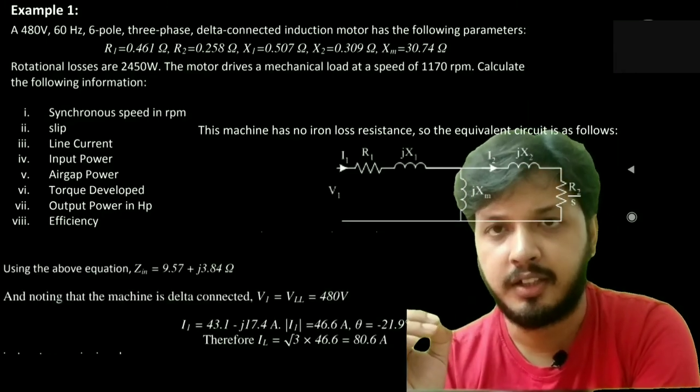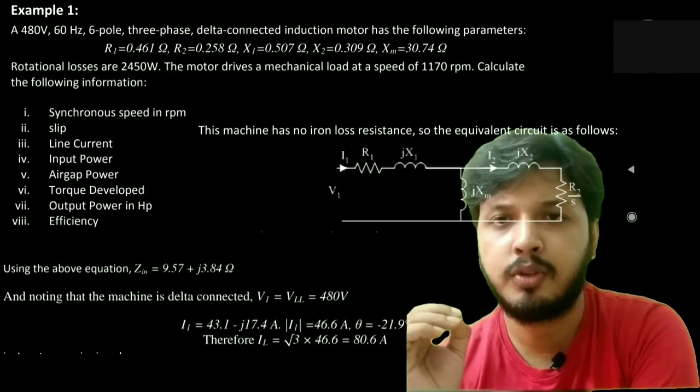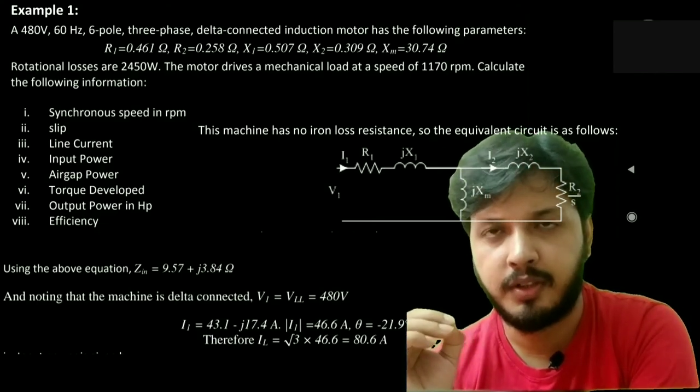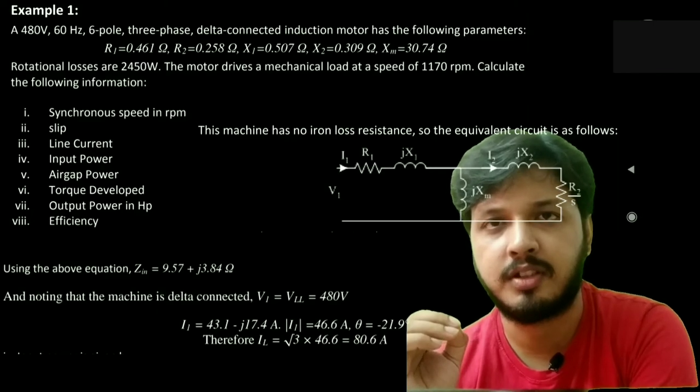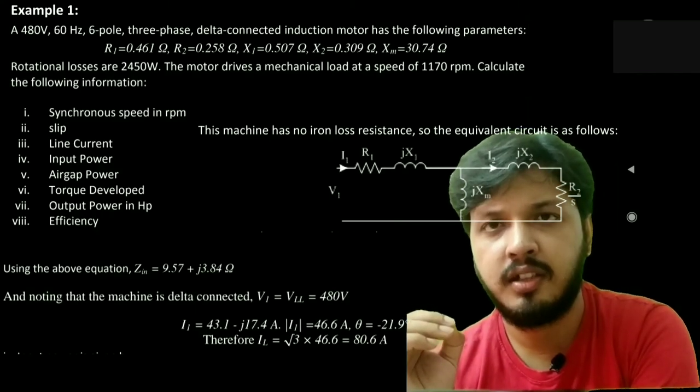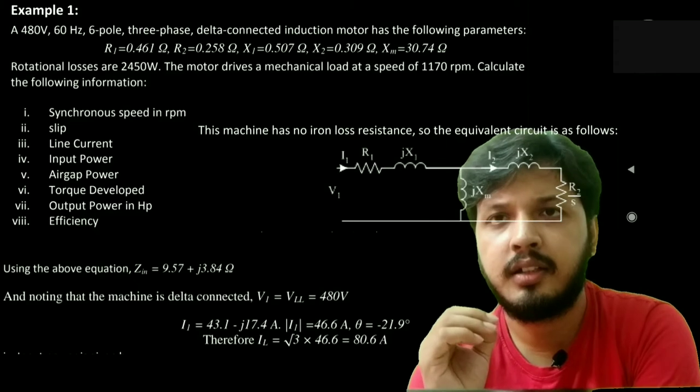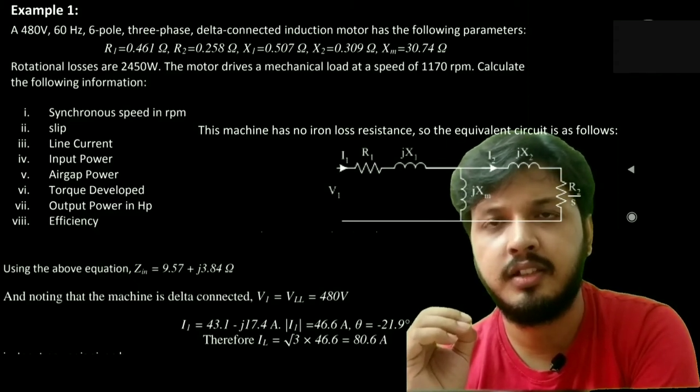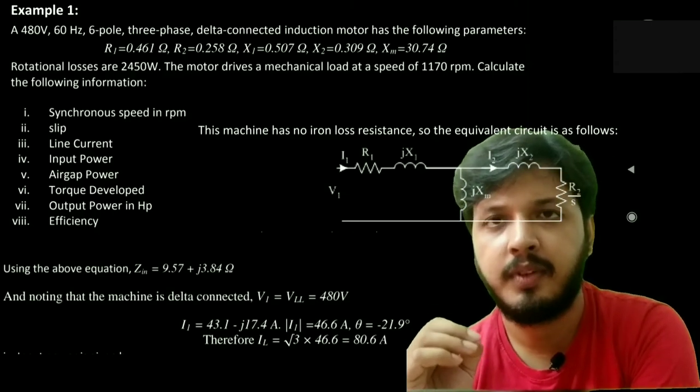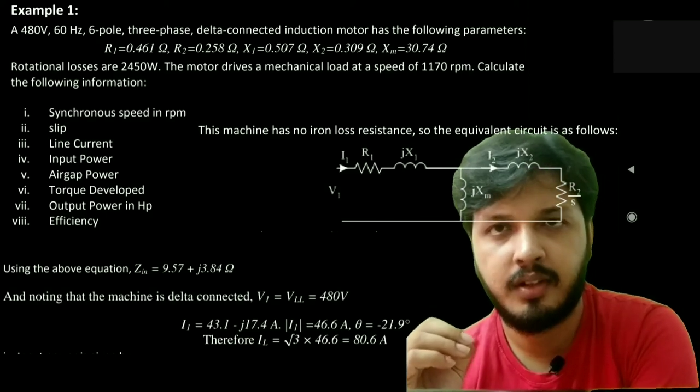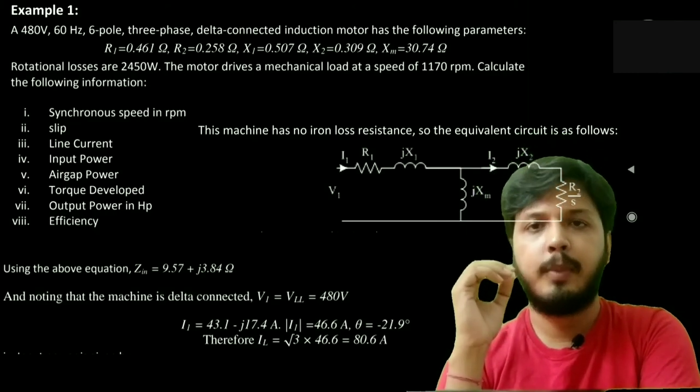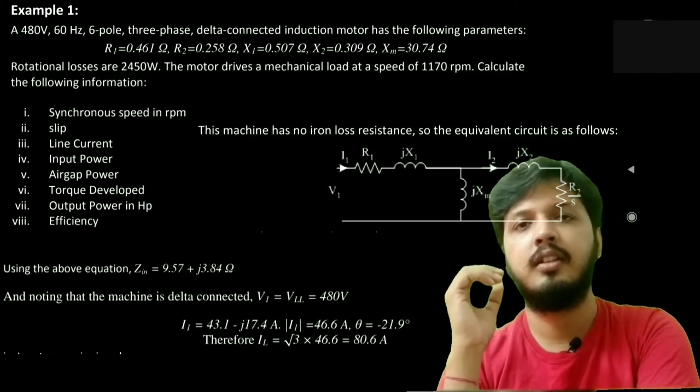Now the machine is delta connected, so its line and phase voltage both are equal, that is 480 volt. Putting the value of voltage 480 volt and impedance 9.57 plus j3.84 ohm, we'll find that I1 will be 43.1 minus j17.4 ampere. Taking the magnitude of I1, we'll get that it is 46.6 ampere and theta is minus 21.9 degree. This minus sign indicates that current is lagging the voltage. As this is delta connected, the line current will be root 3 times phase current.